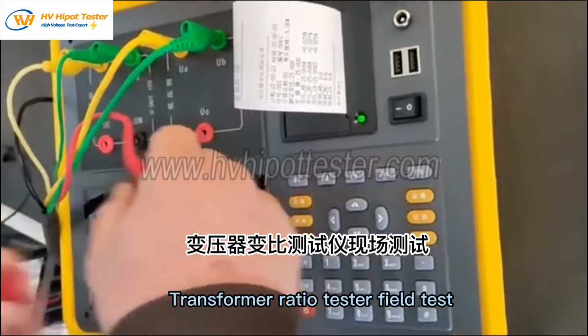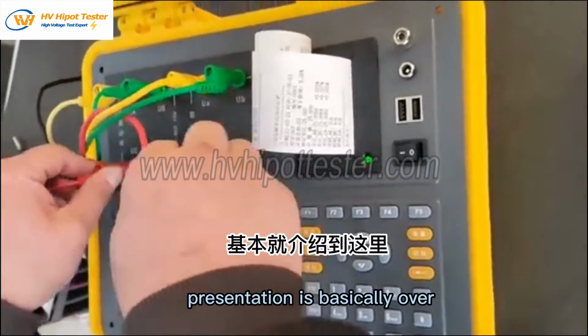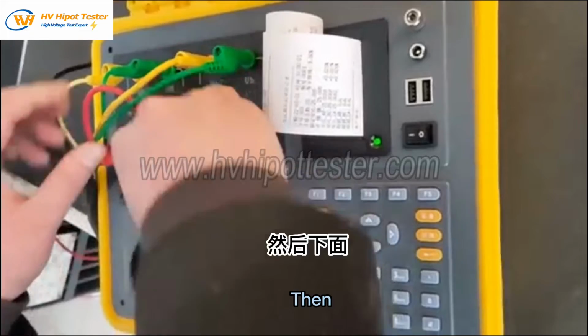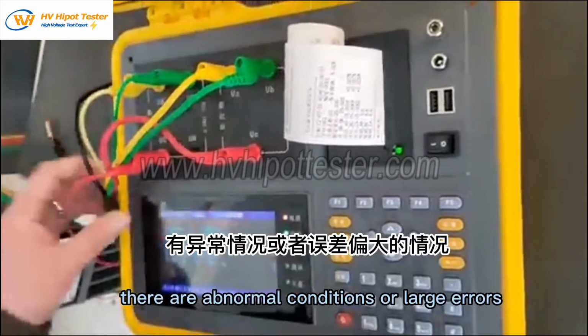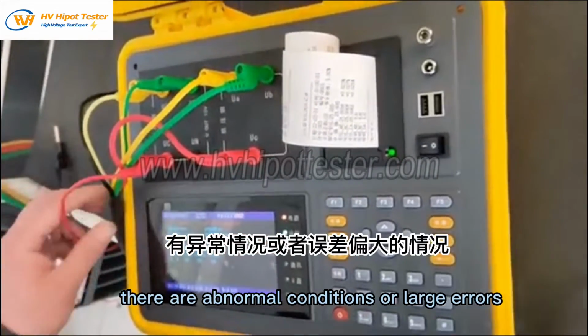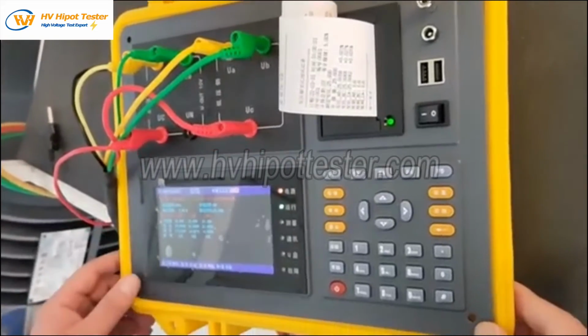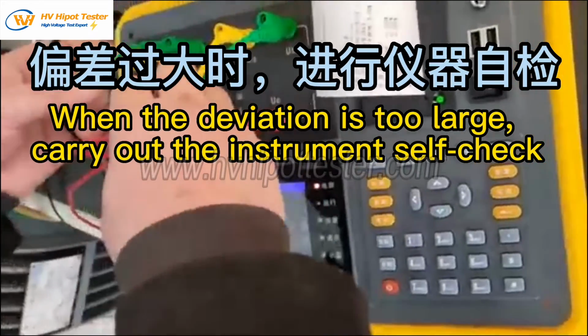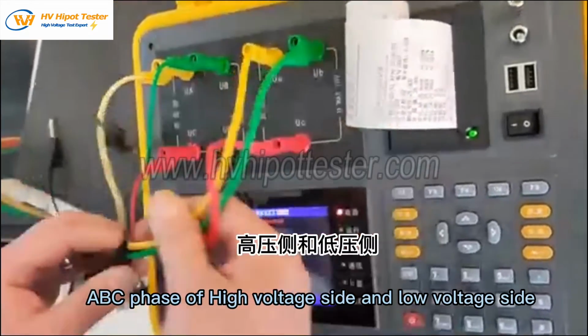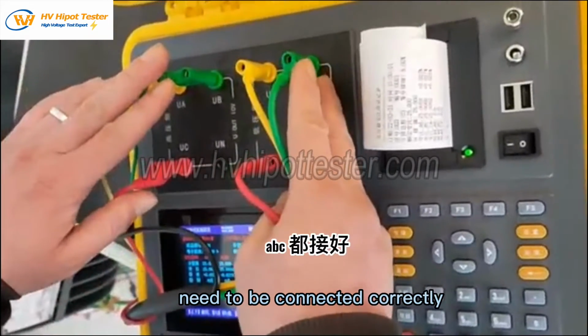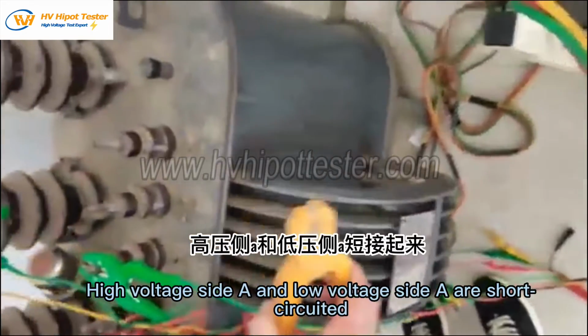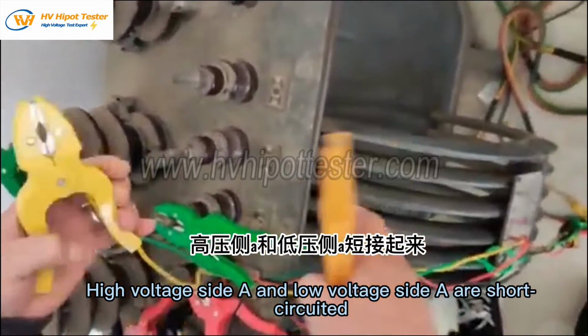Transformer ratio tester field test presentation is basically over. Then, if at site there are abnormal conditions or large errors, we can perform instrument self-test. ABC phase of high voltage side and low voltage side need to be connected correctly. Test clamp of high voltage side A and low voltage side A are short-circuited.